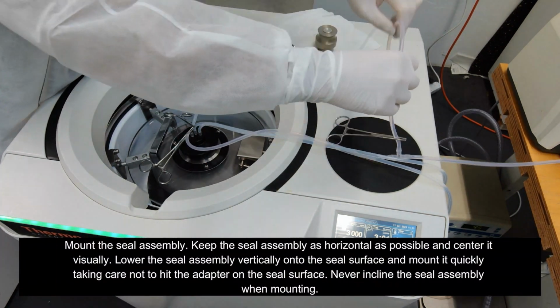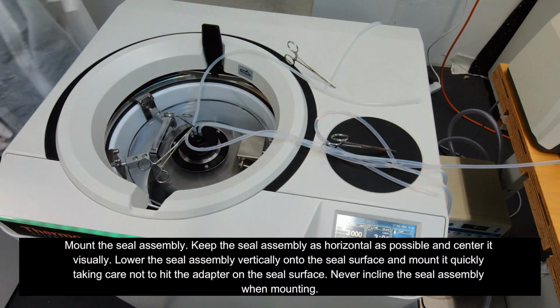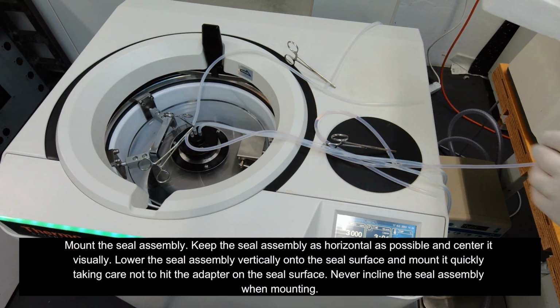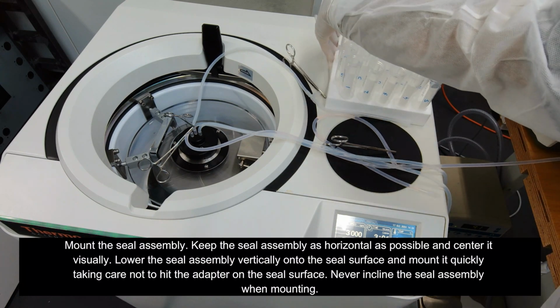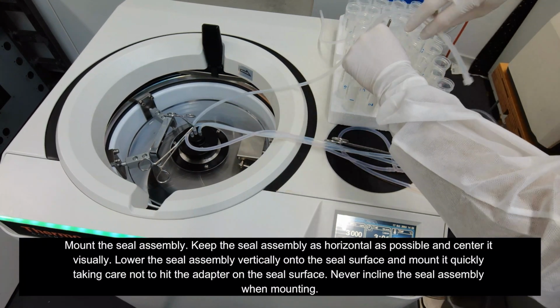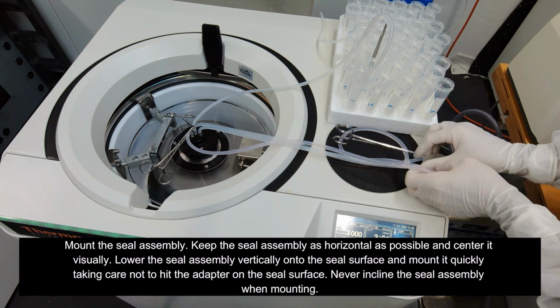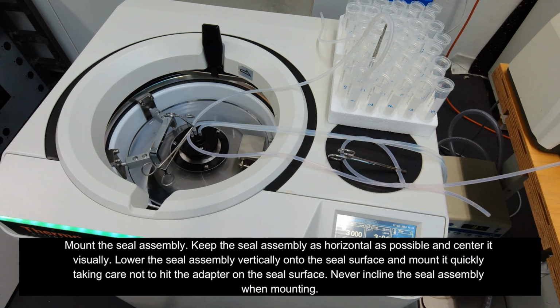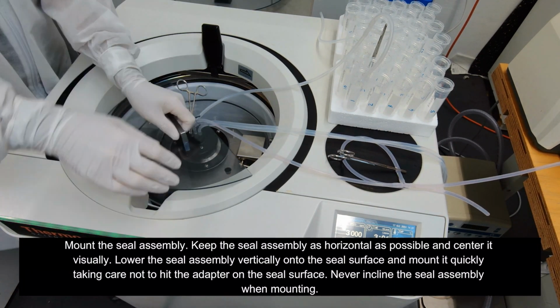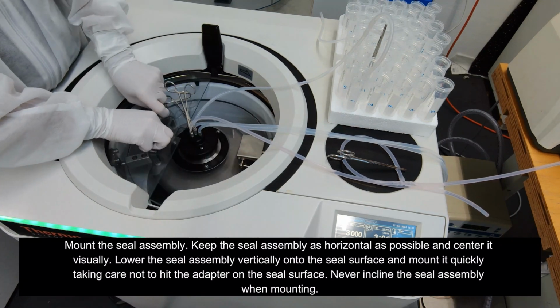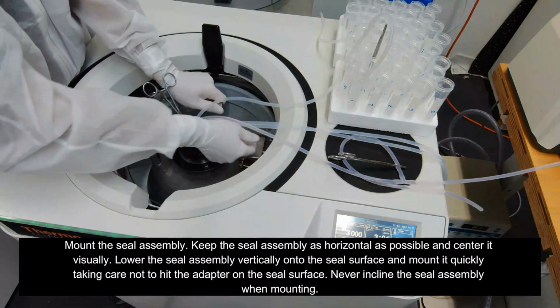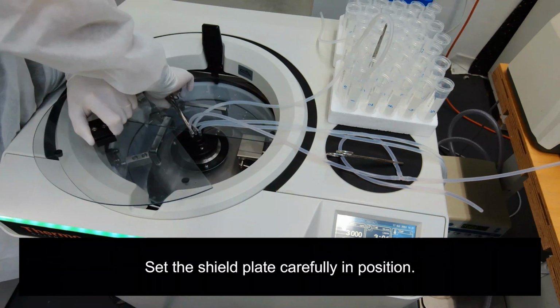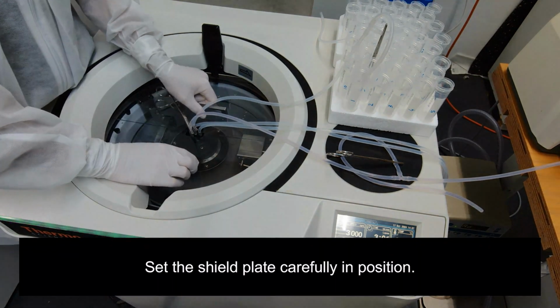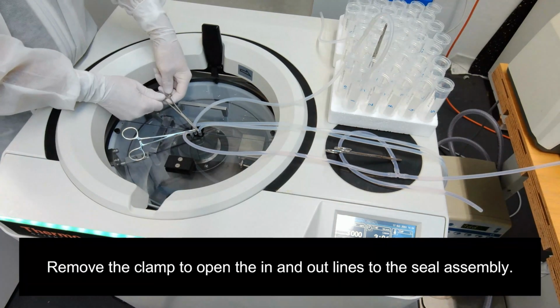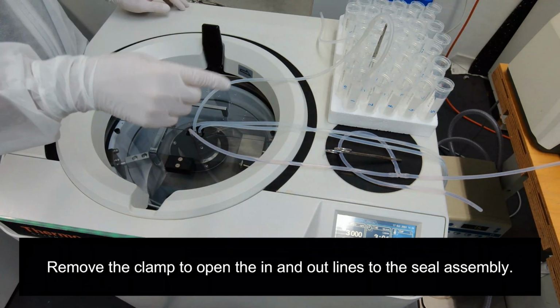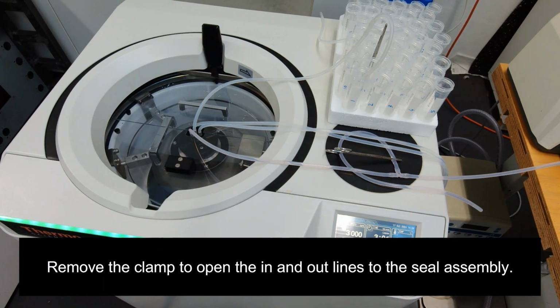Mount the seal assembly. Keep the seal assembly as horizontal as possible and center it visually. Lower the seal assembly vertically onto the seal surface and mount it quickly, taking care not to hit the adapter on the seal surface. Never incline the seal assembly when mounting. Set the shield plate carefully in position. Remove the clamp to open the in and out lines to the seal assembly.